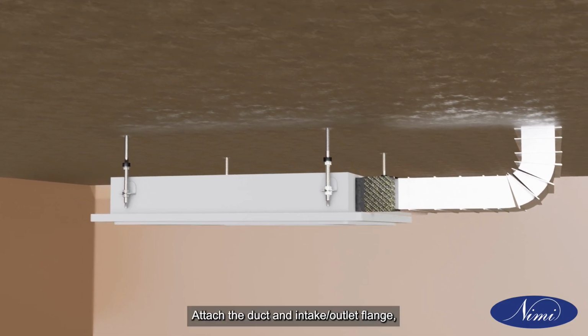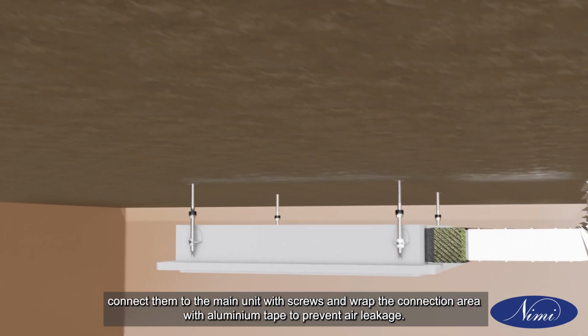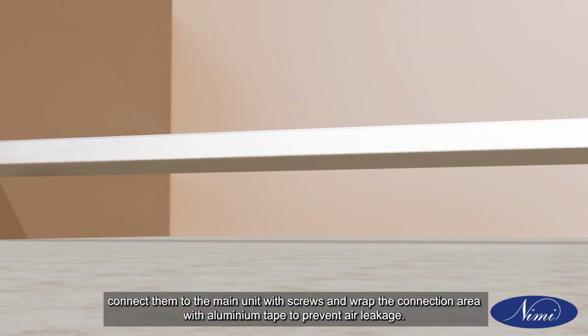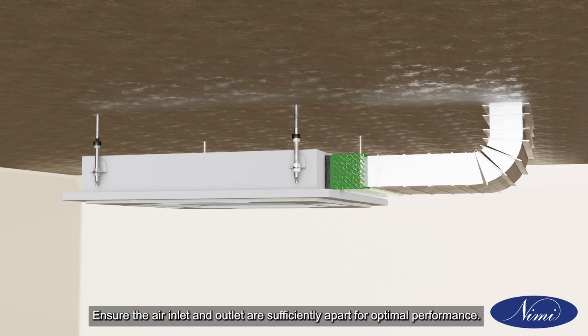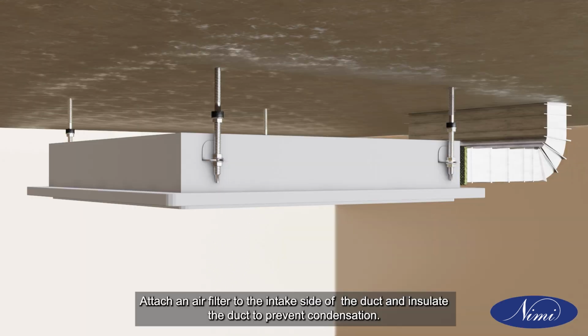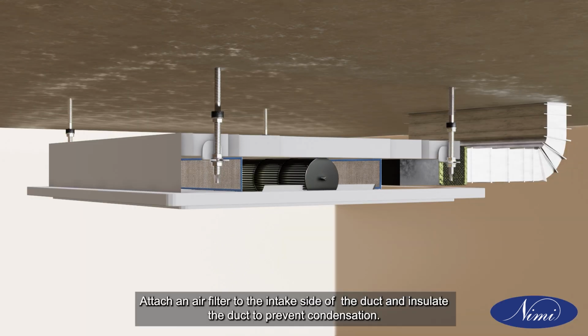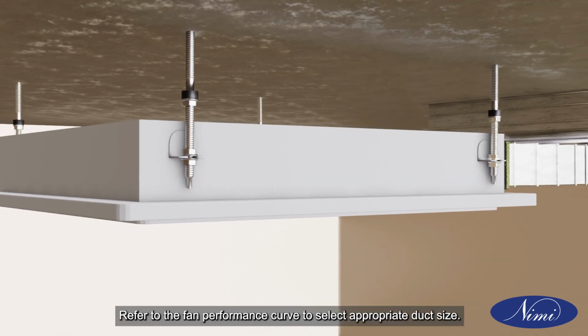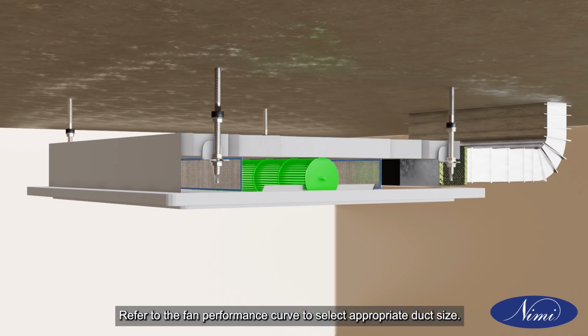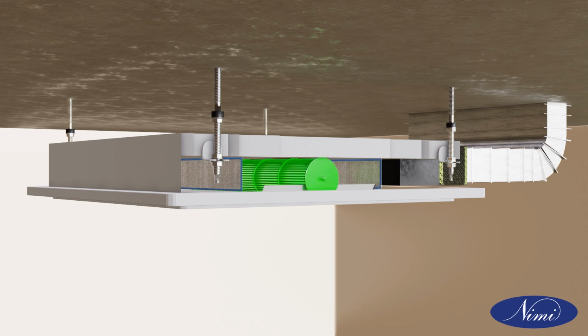Attach the duct and intake outlet flange, connect them to the main unit with screws, and wrap the connection area with aluminium tape to prevent air leakage. Ensure the air inlet and outlet are sufficiently apart for optimal performance. Attach an air filter to the intake side of the duct and insulate the duct to prevent condensation. Refer to the fan performance curve to select the appropriate duct size.